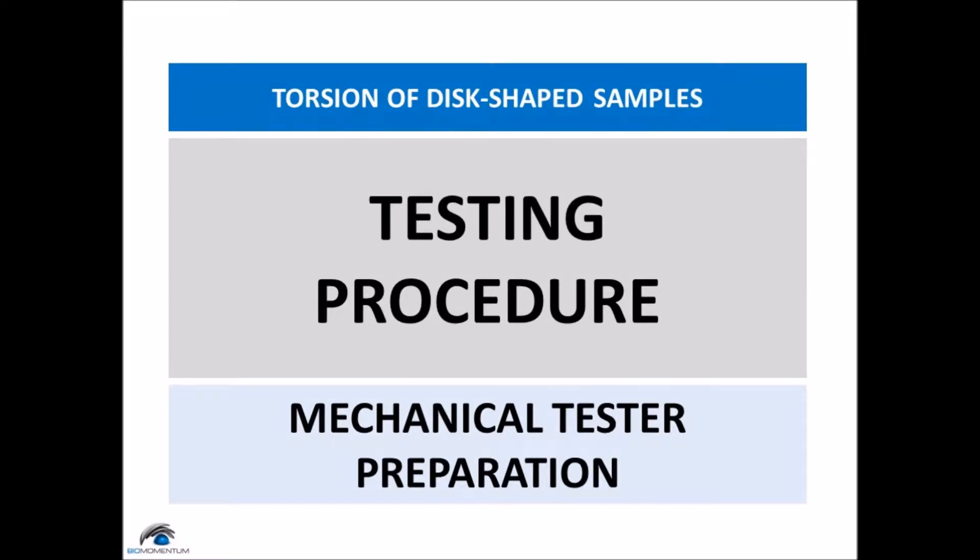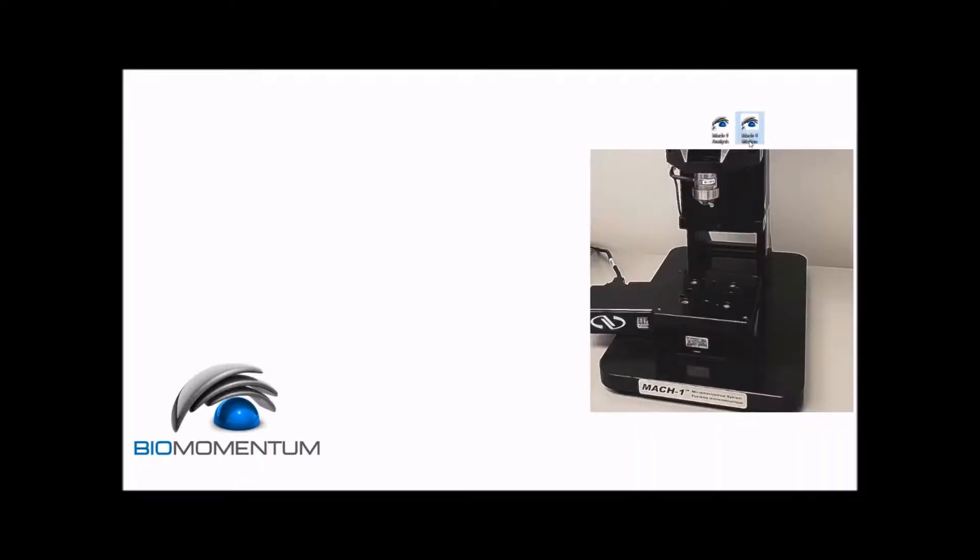And now, the testing procedure for the mechanical tester. Open Mach-1 Motion software and select the proper configuration. In this case, we have a vertical stage and a rotational stage, which corresponds to the model V500CT.